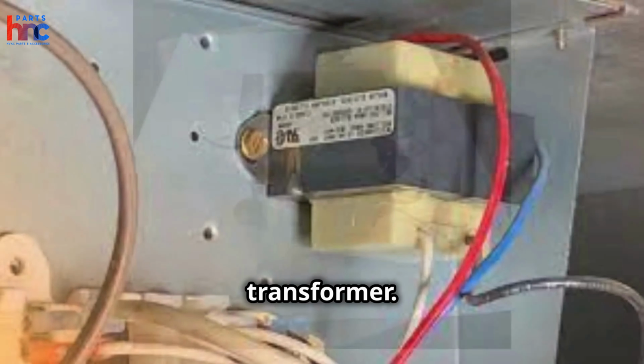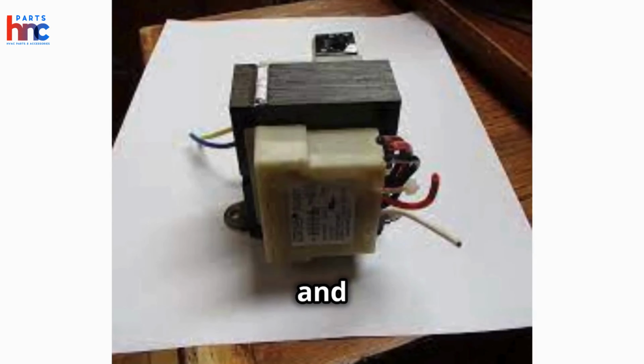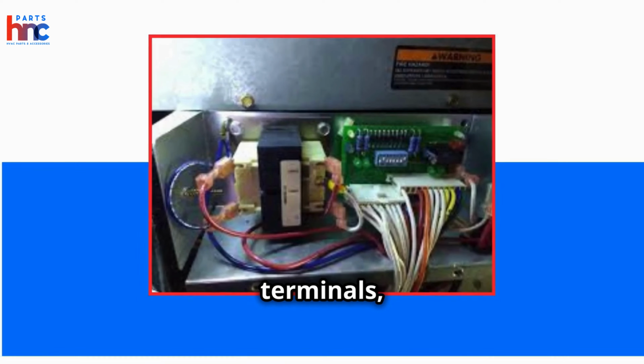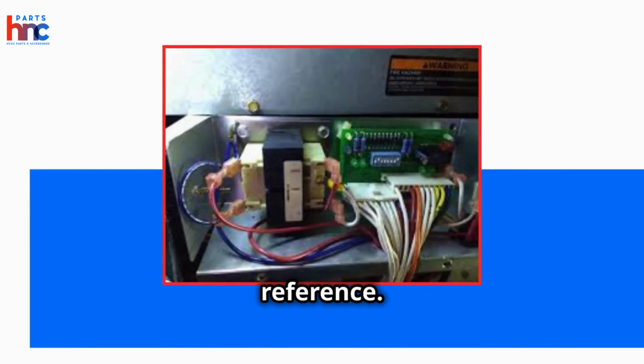If the transformer is faulty, you'll need a compatible replacement. Take a photo of the wire connections before removing the old transformer. Disconnect the wires and remove the faulty transformer. Install the new transformer by connecting the wires to the correct terminals, using your photo as a reference.